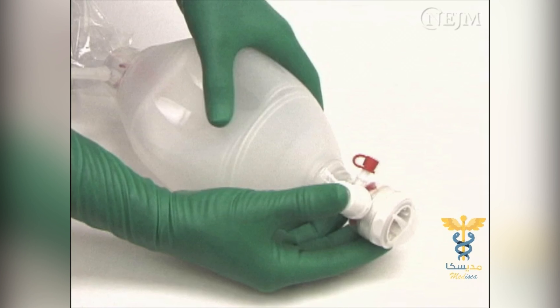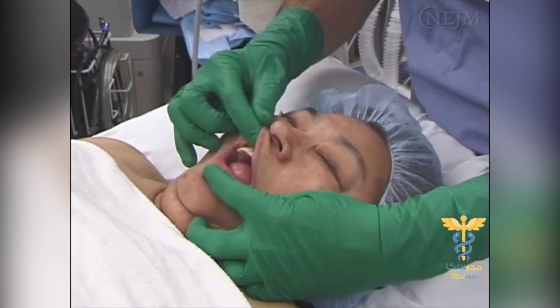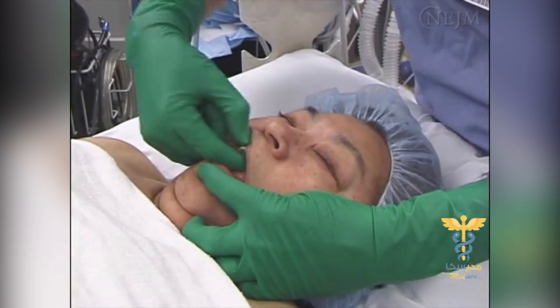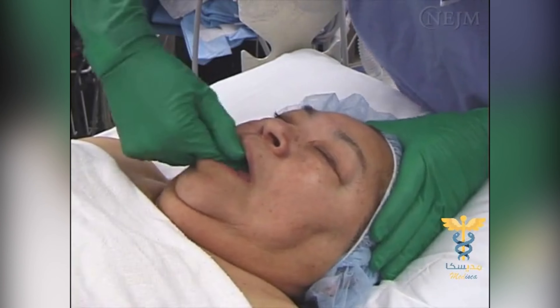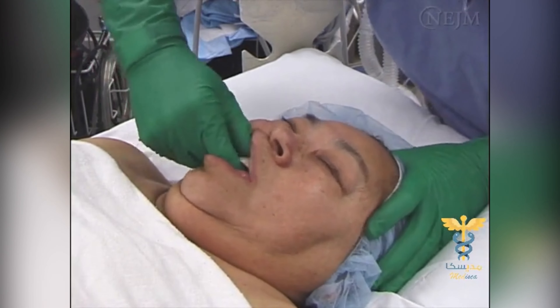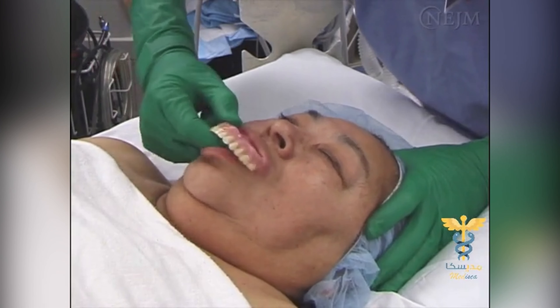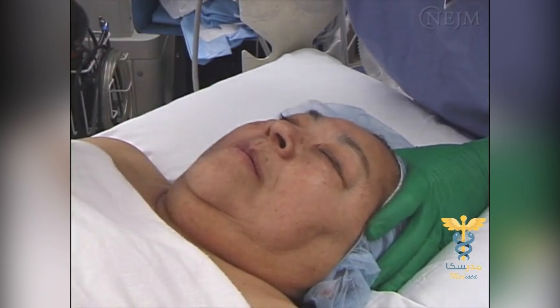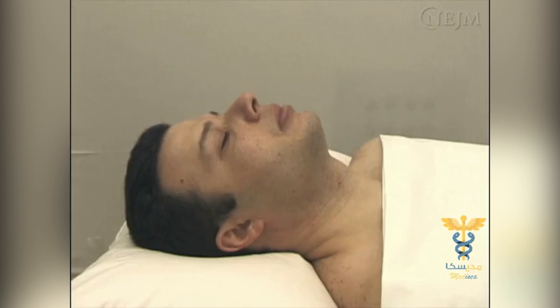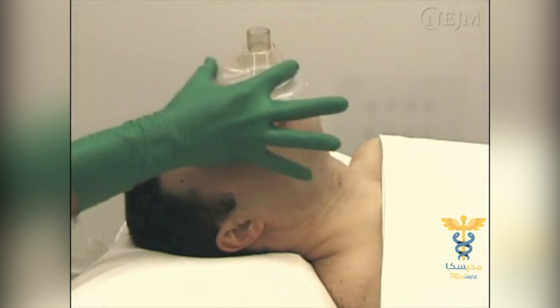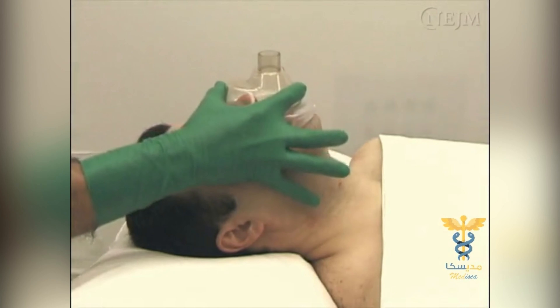The connector of the mask is a standardized 22mm diameter orifice and connects the mask to a bag valve device. To maintain a good seal, it is imperative for the mask size and shape to conform to the facial anatomy. This is particularly important in the pediatric population. Thus, several masks, shapes, and sizes should be readily available.